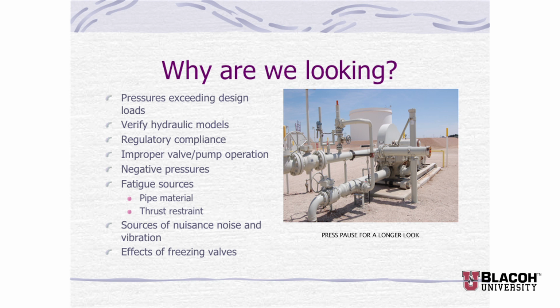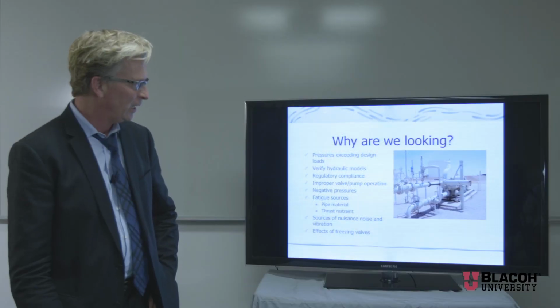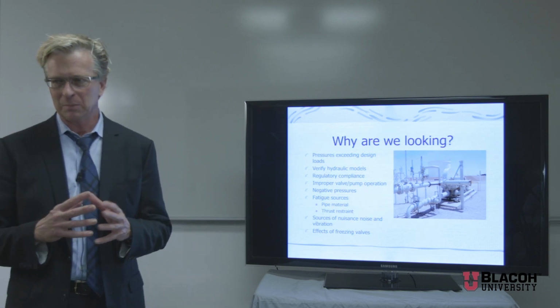We have one in particular where their control valves are creating problems. They looked at their pumps, they looked at pump trips, they looked at the delivery system. In this case, it was to rail cars and barges. They had no problem, all is well. That was all the input data in the model, and then we started having failures. So we hooked up our computer, and everything would be fine, and then the pump is running, loading a system, nothing should be happening, and then all of a sudden we get this negative transient wave coming through the piping system at like -8, okay? Which isn't supposed to be there.